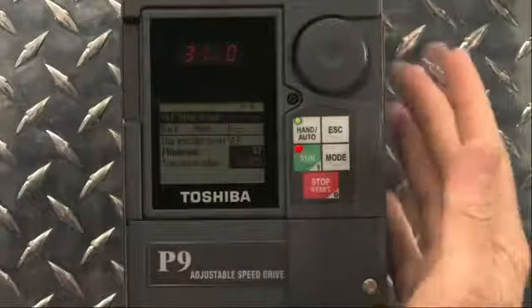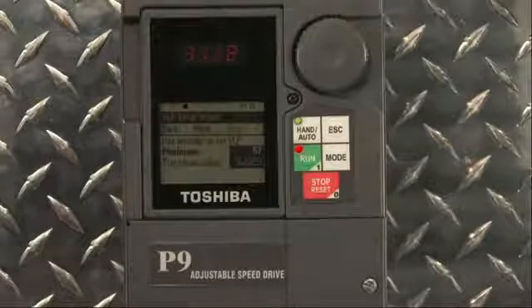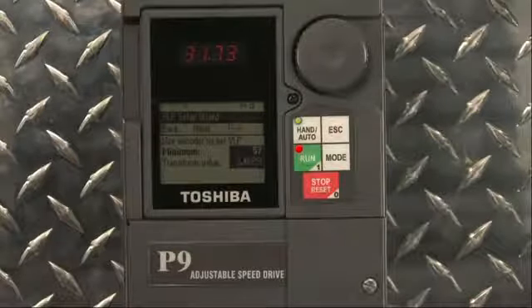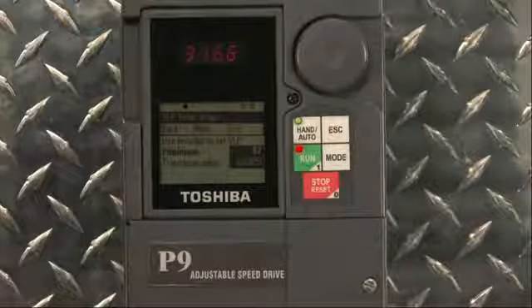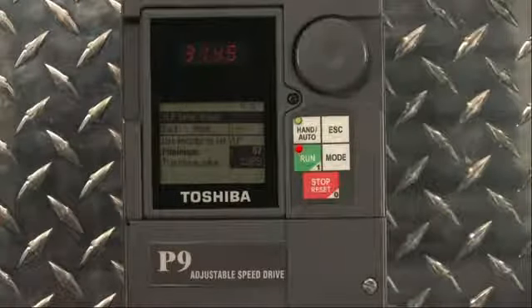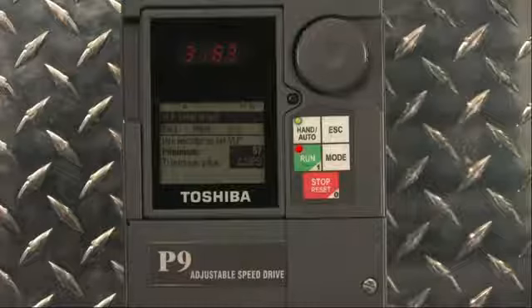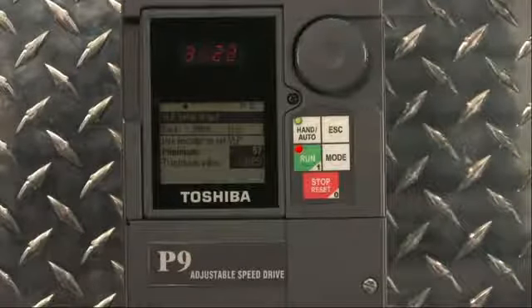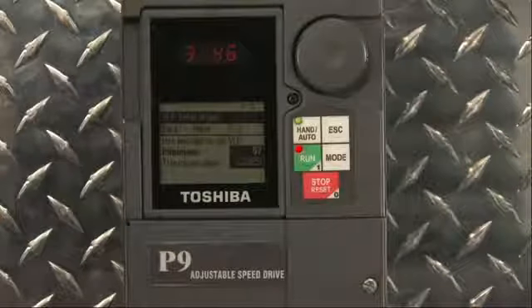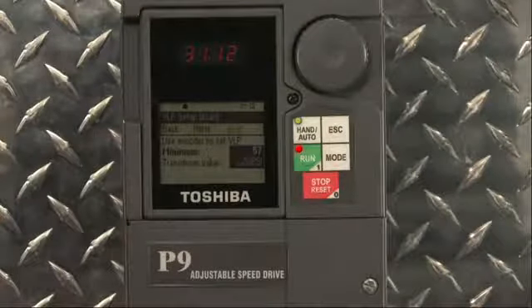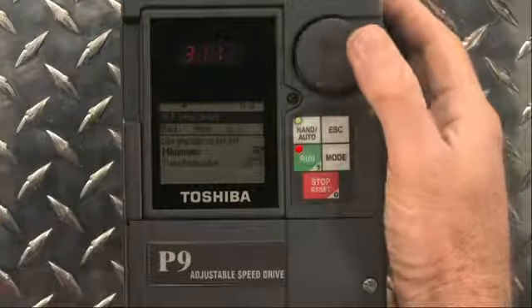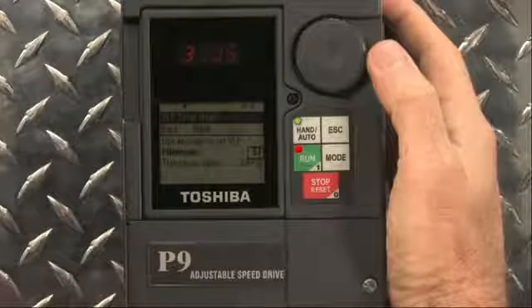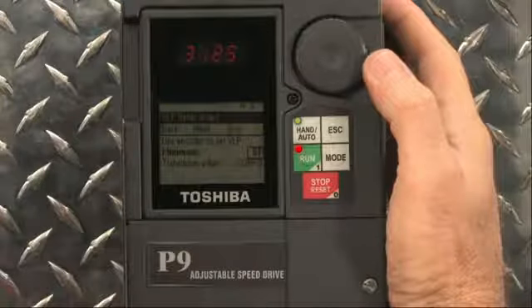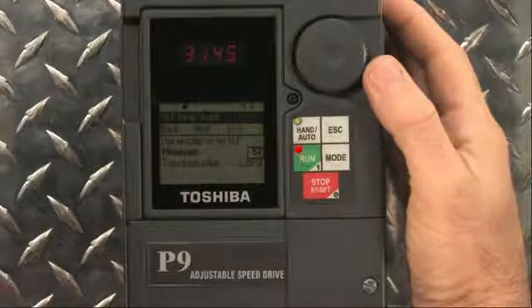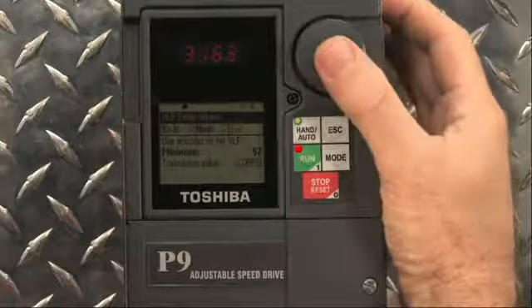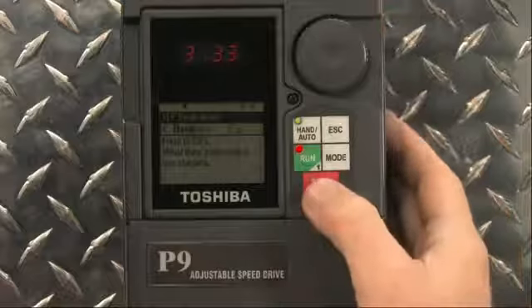We will continue to lower this number until one of three things happen. 1. The pump begins to stall or surge. 2. The system pressure falls well below the operating pressure of the system during normal operation. 3. The red LED display indicates an output frequency between 31 and 32 Hz. For this demonstration, the output frequency between 31 and 32 Hz will be the criterion first met. Once this occurs, press Enter. The VLP minimum number will indicate the pump's minimum flow and will be the lower limit of pump operation. Let's make note of this number as we did with the VLP maximum number. Now we'll scroll to the next option and press Enter.